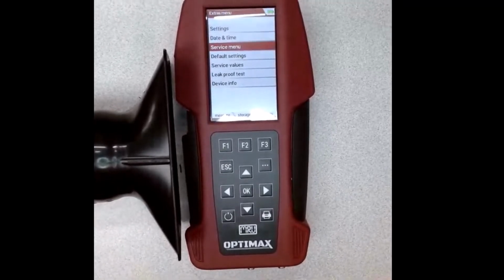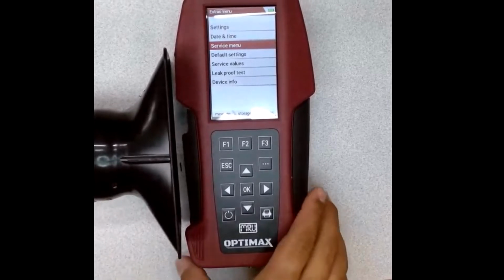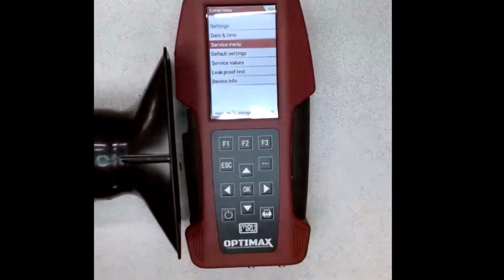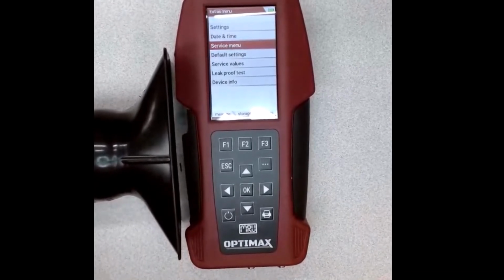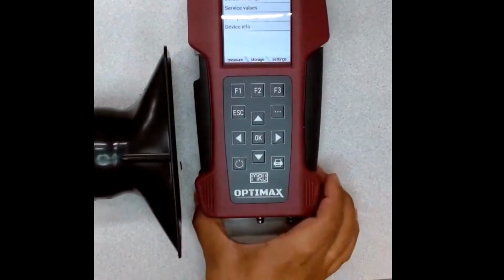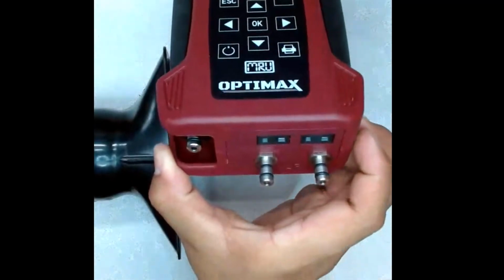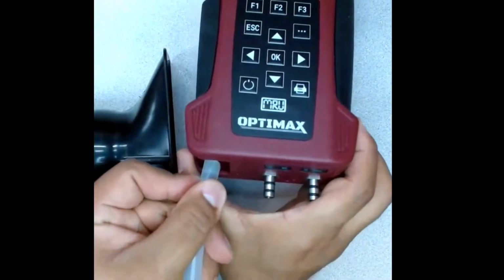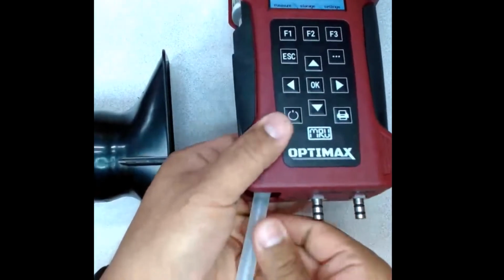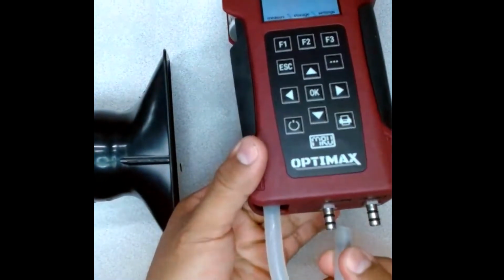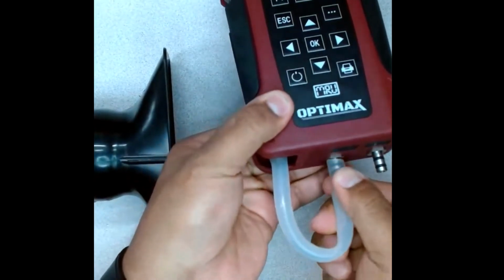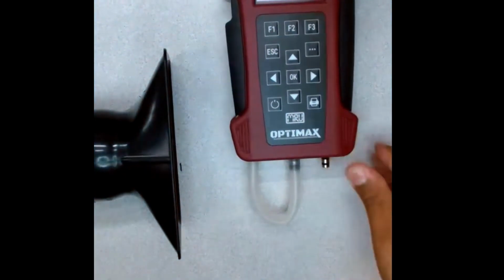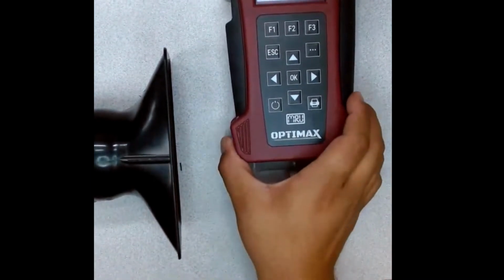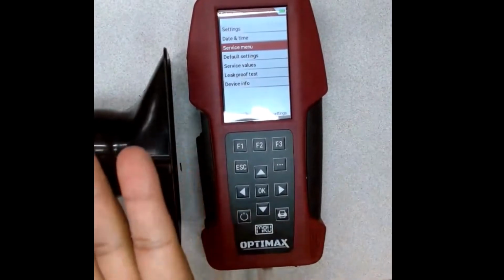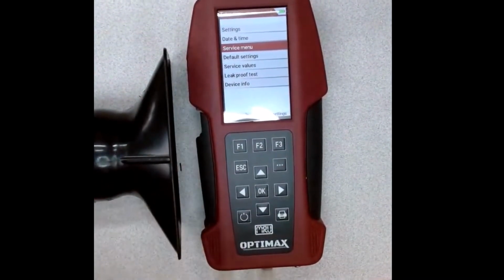So another step that we usually take is what we call a leak test, and it's an internal check for the analyzer, so it can check its own internals for leaks. Usually, how we do that is with the ports on the bottom. So from the gas inlet, which is here on the left, we use just a short hose to bridge across to one of the pressure inlets. And essentially what the analyzer does with the leak test is it pulls against its own pressure sensor.